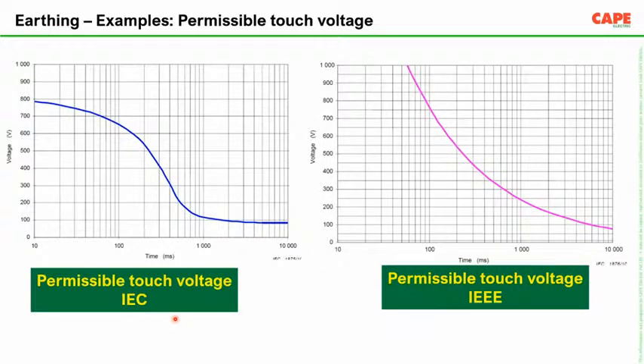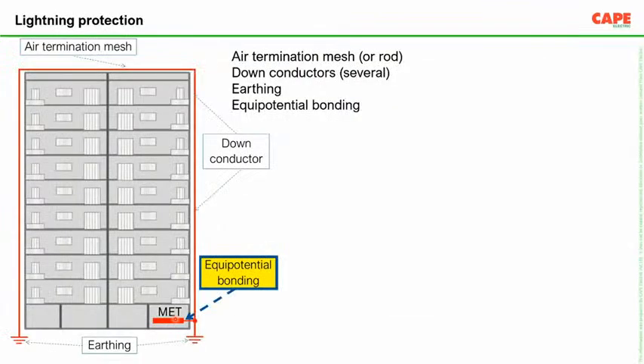Whereas the permissible touch voltage followed in IEEE is a little bit different, but there is nothing to worry about it. Basically, both are safe. IEC is more stringent, so to follow the curve of IEC, we have to make a much more perfect installation. So basically the earthing is always to protect people, and here the target is to achieve the step and touch voltage lesser than the tolerable limit.